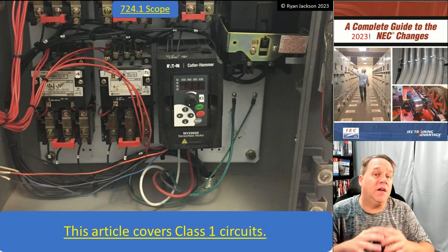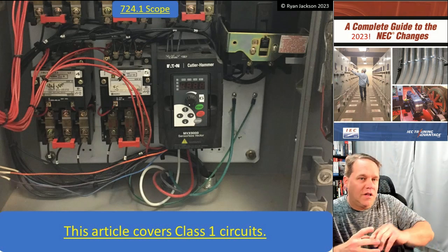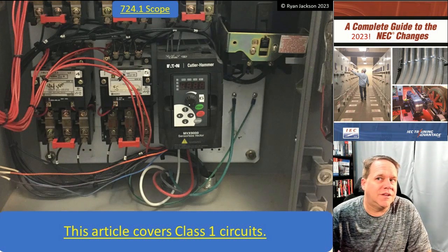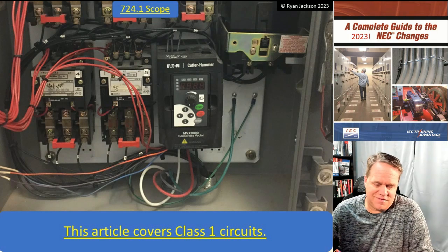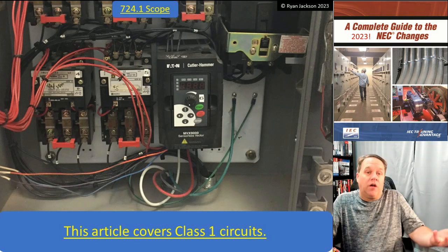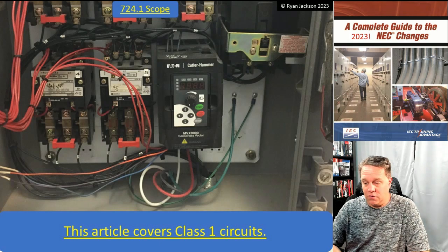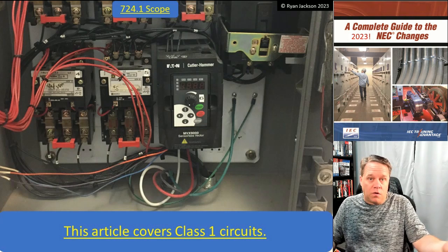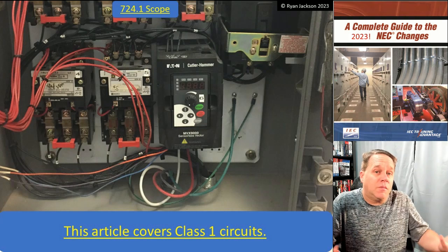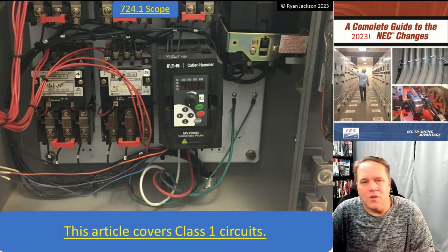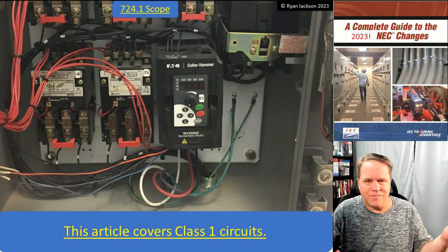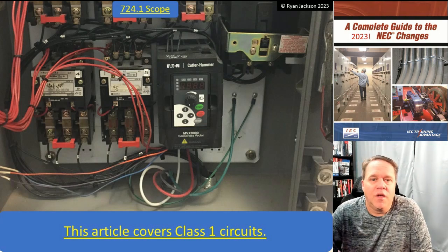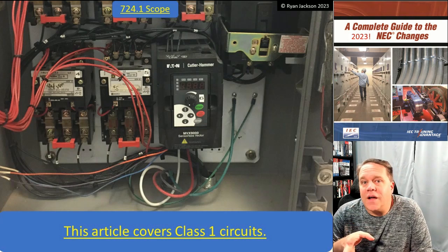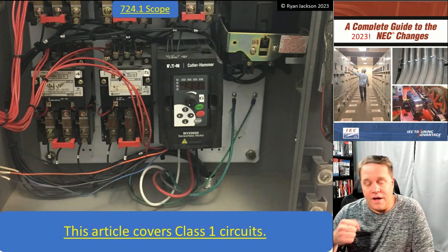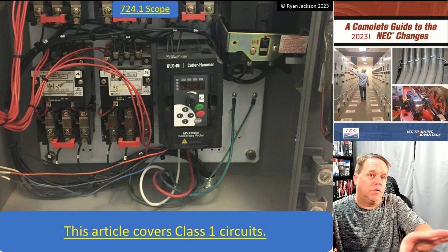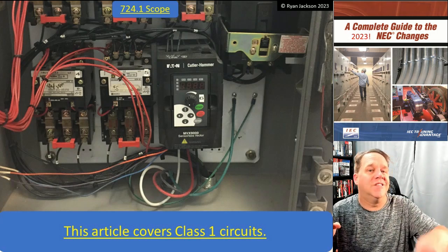So if you have what we historically called a Class 1 control circuit that's higher than 30 volts, like 120, we don't really call that a Class 1 circuit anymore. We just say it's no different than power and lighting. And really that kind of makes sense. I mean, how do you wire a 120 volt motor control circuit? You don't use thermostat cable, right? You're using EMT, or you're using PVC, or you're using MC cable, and you're using THWN conductors. So why do we have to convolute everything? Oh, that's Class 1 non-power limited. Just call it the regular Chapter 3 wiring, because that's how we do it anyway. So Article 724 now only goes up to 30 volts, and as such, I think it's going to be used much less often. I think you're going to have Class 2 and Class 3 in Article 725, and then you're going to have Article 300 covering what we used to call a Class 1 non-power limited circuit.